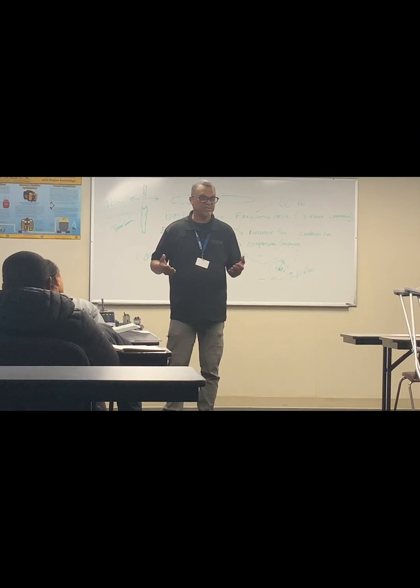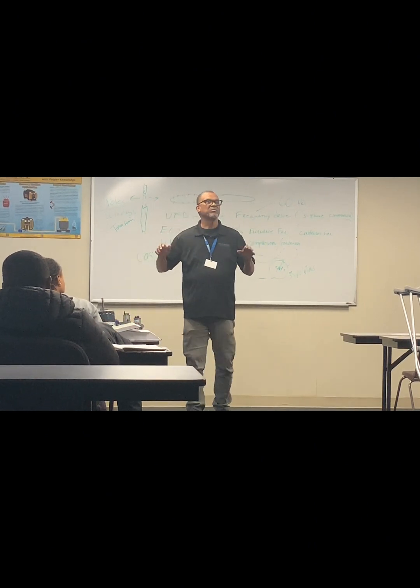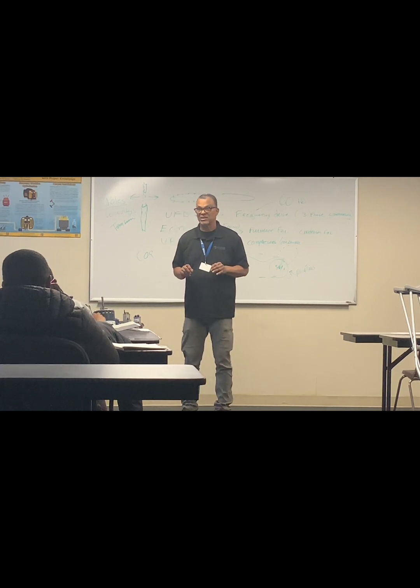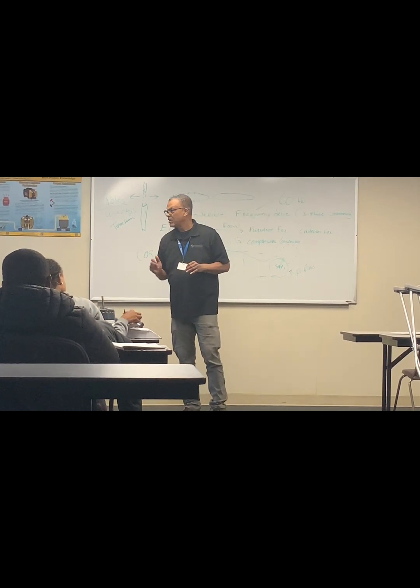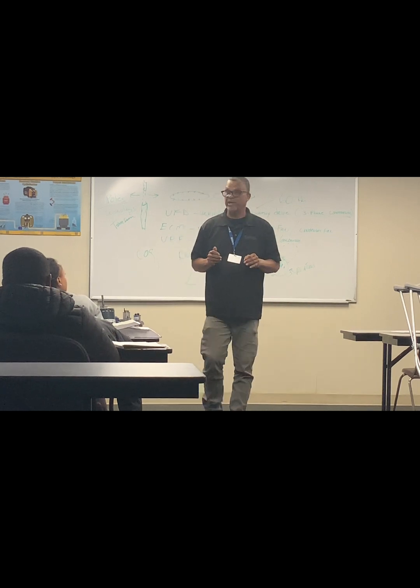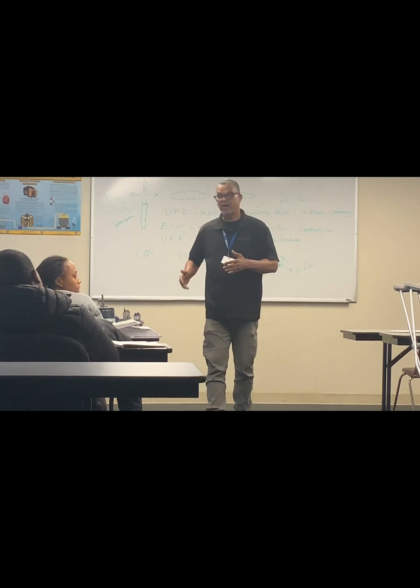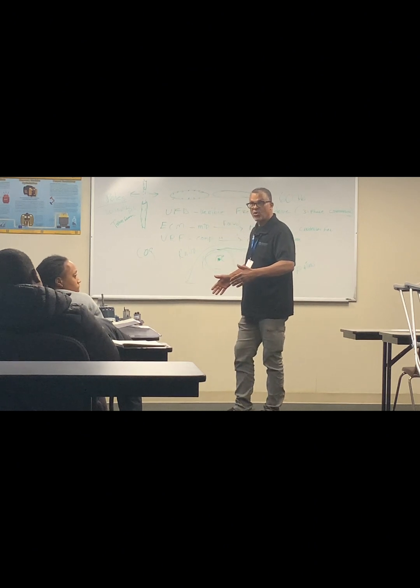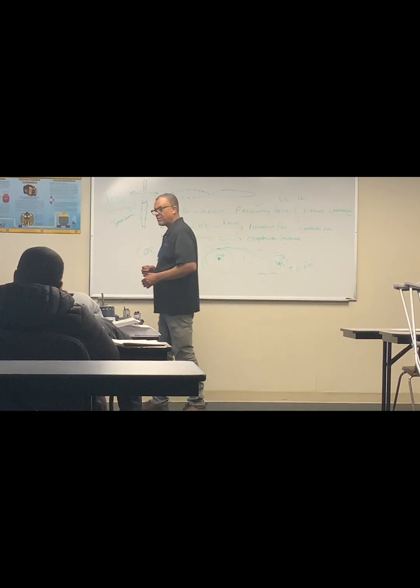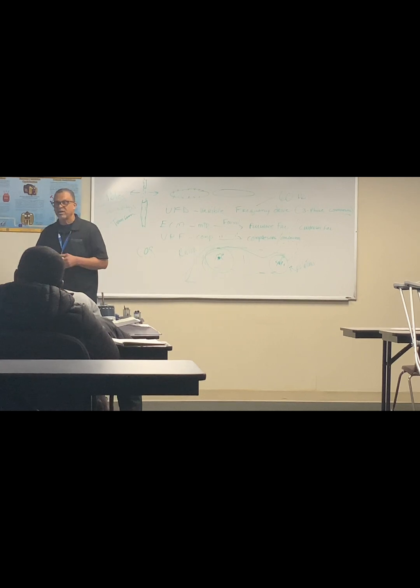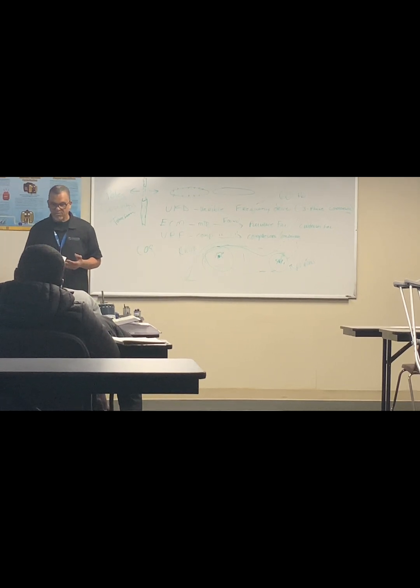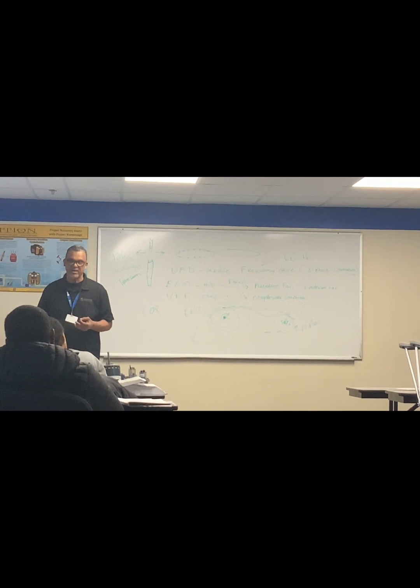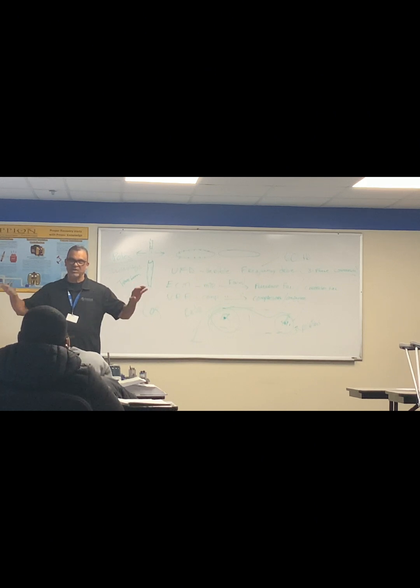The size of some air handlers can be as large as this room. And they could have a blower from that board to here. So it has a large 25 horse motor or 50 horse motor with a bolt in the top of it so you can take it off with a chain. And those motors are made for higher torque or higher demand, because you can imagine in a floor of a hospital how far that air handler has to flow that air in so many different locations. It has to be a very powerful motor.